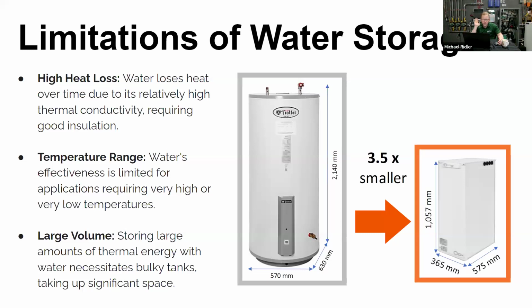The other thing is the effective range at which the water is usable can be a challenge. It's okay in some applications, but the water is not always going to be the best case, because we have to store it at a very high temperature to get usable heat out of it. And in an air-to-water application, I can't produce high temperatures.